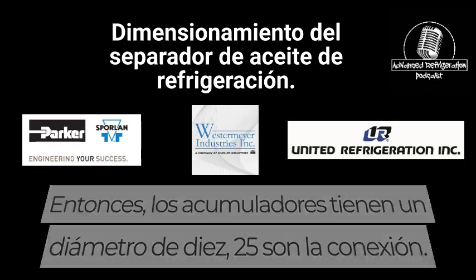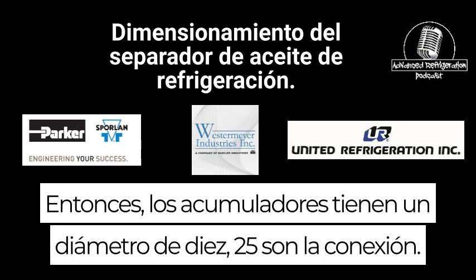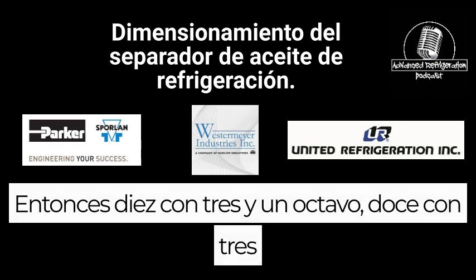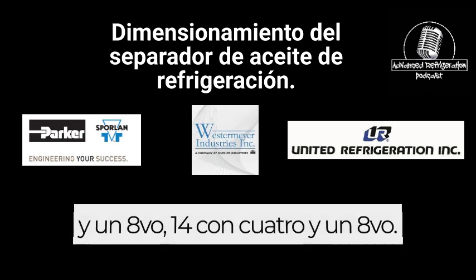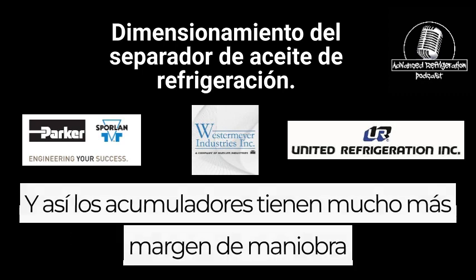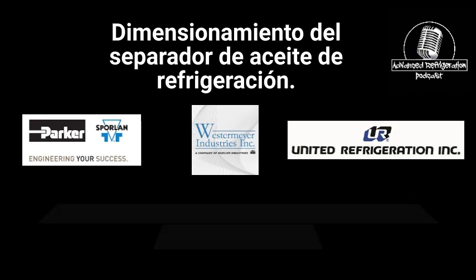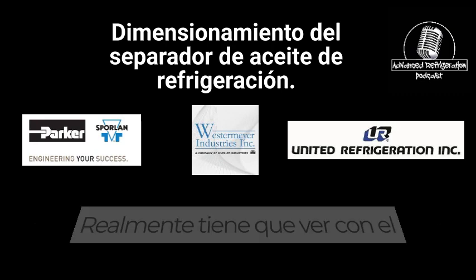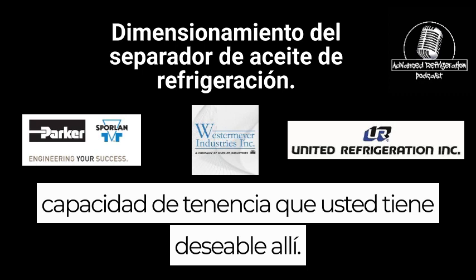There's a handful of models, and I'll just run through them real quick. The A10: accumulators are A, 10 is diameter, 25 is connection. So 10 with 3 and an eighth, 12 with 3 and an eighth, 14 with 4 and an eighth. Accumulators have a lot more wiggle room on the connection size that you can operate with. It really has to do with the holding capacity that you desire.